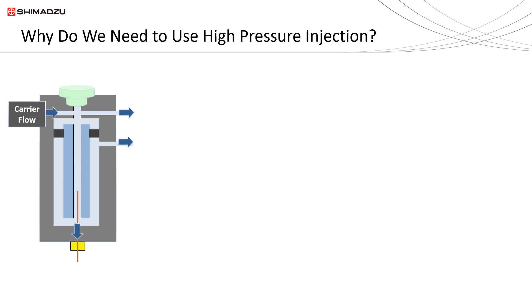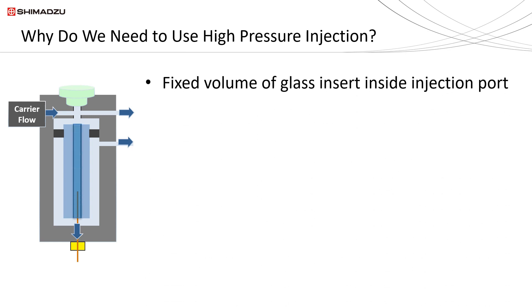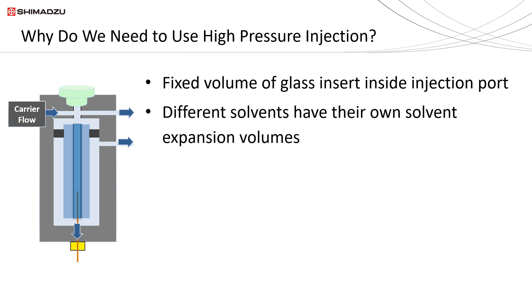Inside the injection port in a gas chromatograph, there is a glass insert installed. The glass insert has a fixed volume depending on the dimension of the glass insert used. When liquid sample is introduced into the injection port, it will get vaporized inside the glass insert. Different solvents have different solvent expansion volumes depending on the type of solvent, injection temperature, injection volume, and column head pressure — which determines how much vapor would be produced from that injection.